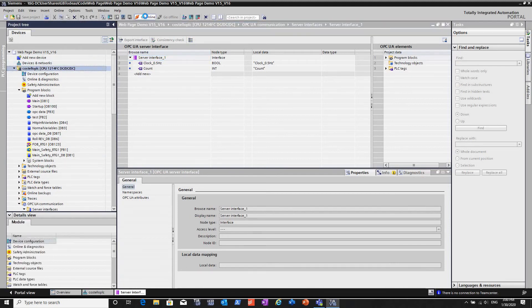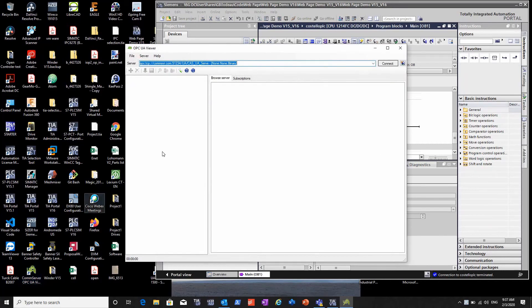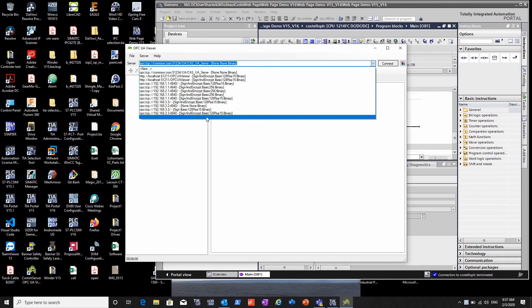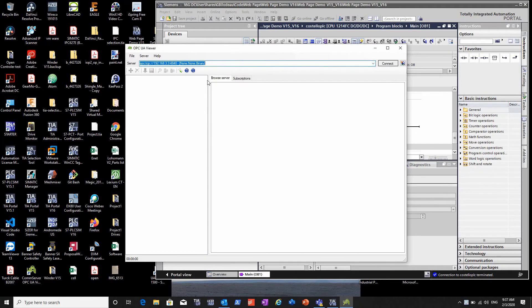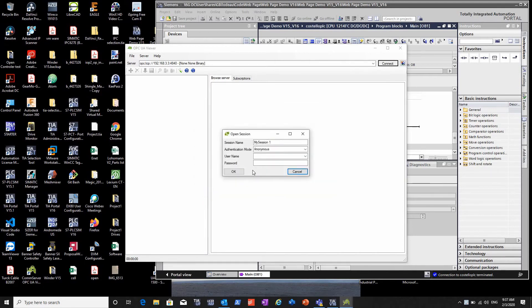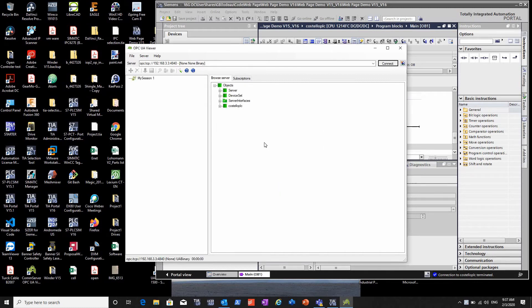Variables can be granularly set down to read-only, write-only, or read-write - these are set for read-write. This is just a free downloadable OPC UA browser - there's lots of them out there on the web. I'm checking on my Windows machine that I can see it. I'm going in anonymous without any user or password because that's how I have the OPC server set up for demo only.